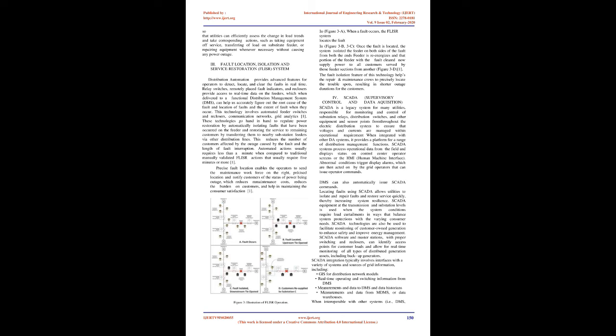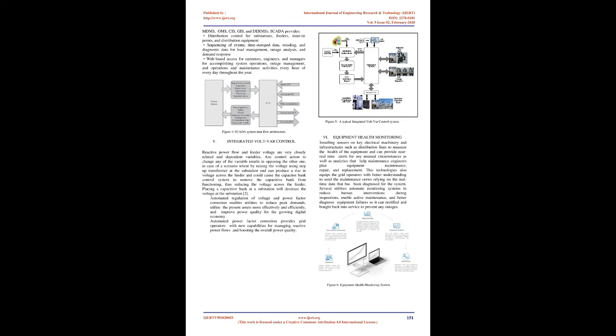This technology involves automated feeder switches and reclosers, communication networks, and grid analytics. 1. These technologies go hand in hand to regulate power restoration by automatically isolating faults that have occurred on the feeder and restoring the service to remaining customers by transferring them to nearby substation feeders via other distribution lines. This reduces the number of customers affected by the outage caused by the fault and the length of fault interruption. Automated actions usually require less than a minute when compared to traditional manually validated FLISR actions that usually require 5 minutes or more. 1.